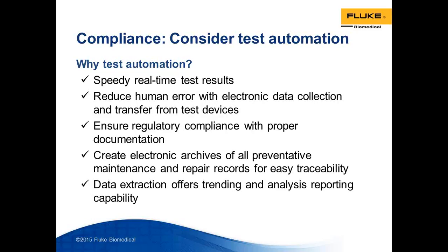So what test automation allows you to do is, essentially, there are a number of ways of looking at it, but the most common is the front end, which is you connect your infusion pump to an analyzer, which automatically drives the pump and extracts the reading. The second piece of test automation is when the analyzer gets the reading, it gives you a consolidated report.